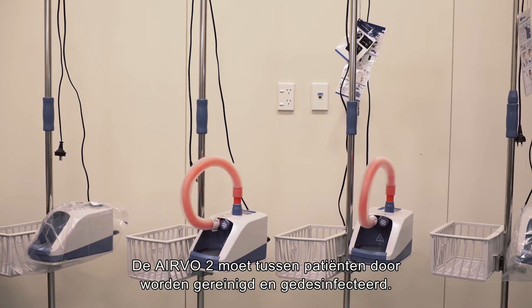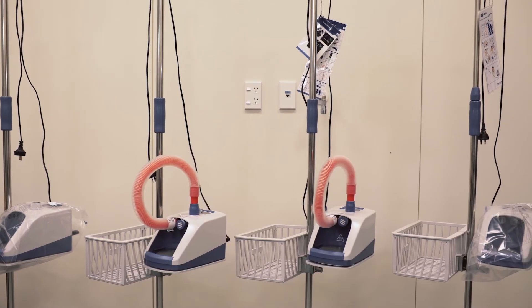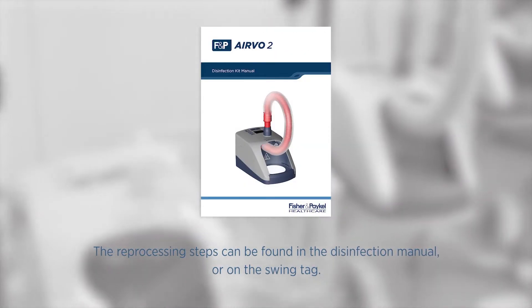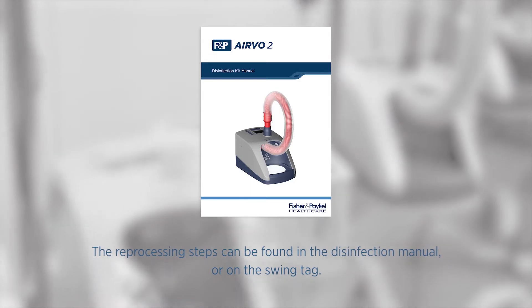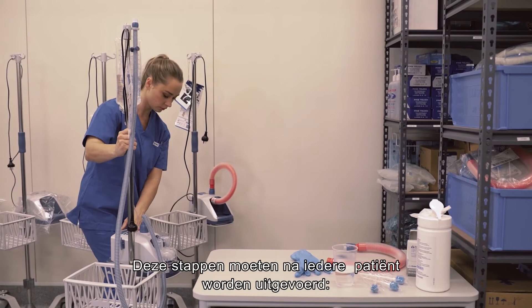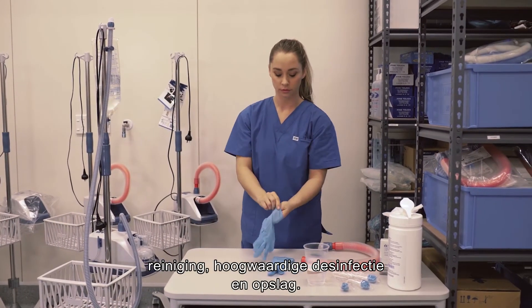The AIRVO 2 must be cleaned and disinfected between patients. This should take place as soon as possible after use. The reprocessing steps can be found in the disinfection manual or on the swing tag. These steps must be carried out between patients: cleaning, high-level disinfection and storage.